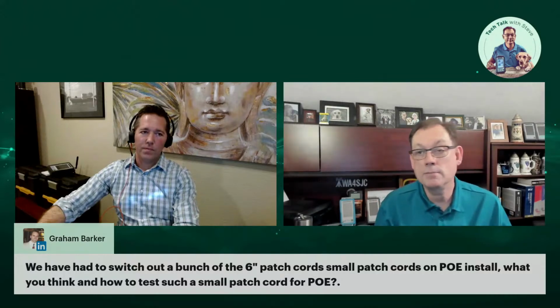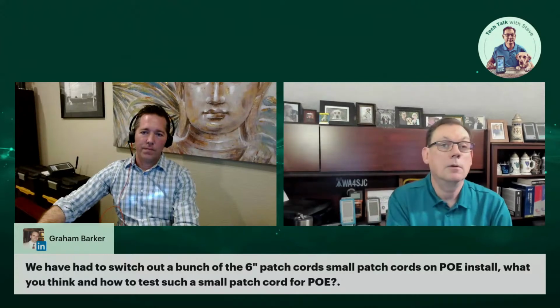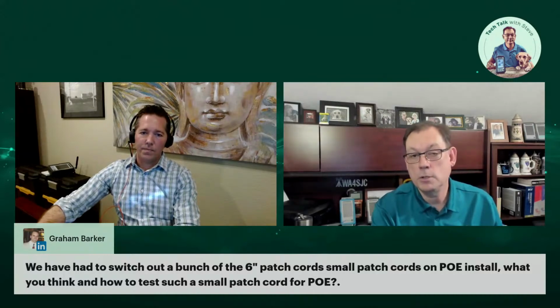A good example: if you've got a short 30-foot run for PoE, typically at 30 feet you're not going to lose much power, so it's probably not a big issue. But say you've got 10 feet of patch cord at one end and 7 feet at the other—now the patch cords are a much bigger portion of the overall cable run. If those patch cords have resistance problems, they'll have a much bigger impact on PoE delivery at the endpoint. If that resistance unbalance is really out of whack, it impacts PoE delivery because power isn't delivered evenly across the pairs. That's when equipment can start to heat up, malfunction, and all kinds of things can go wrong without proper resistance.